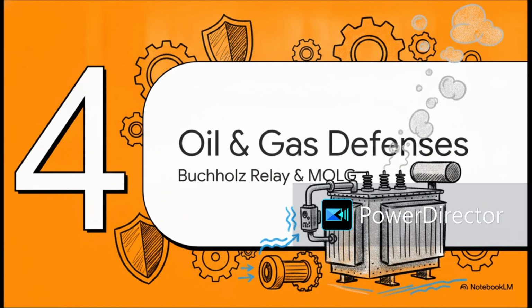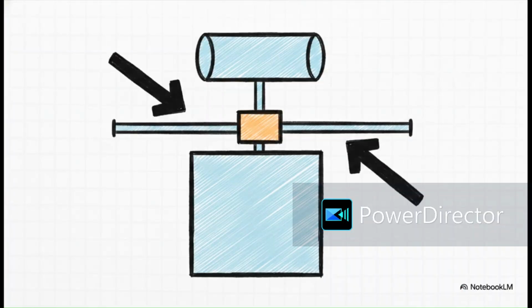Okay, Section 4. Oil and gas defenses, the Buchholz relay, and MOLG. Stepping into the physical mechanics now, these are absolutely critical for oil-filled transformers above 500 kVA. And the undisputed star of the show here is the Buchholz relay. For any field technicians out there, I want you to build an accurate mental map of this hardware. The Buchholz relay is physically mounted right on the connecting pipe between the main tank, which holds the core, and the conservator tank sitting up top. Its exact physical location is the key to how it does its job.